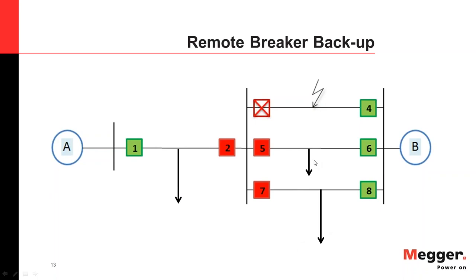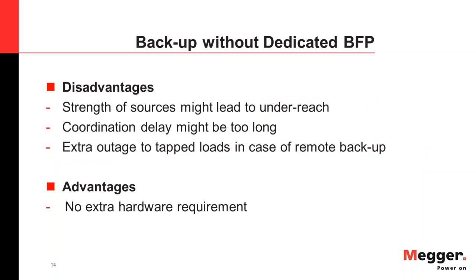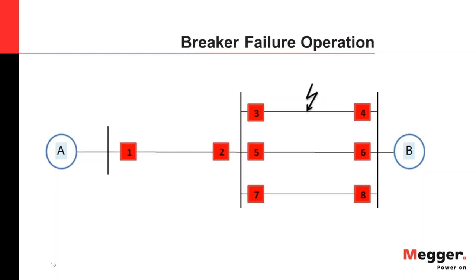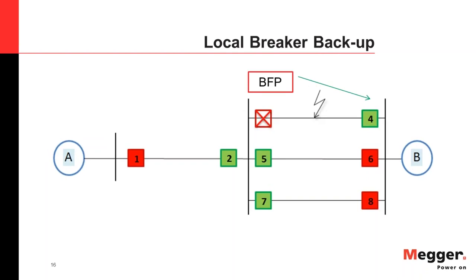The third disadvantage involves tap loads. If you take out Breaker 1, or Breakers 6 or 8, you are causing an outage to all loads connected on those taps, meaning no supply to those consumers. You don't want other loads affected by a fault that happened between Breaker 3 and 4. The only advantage of the remote backup scheme is that it does not require additional hardware equipment.